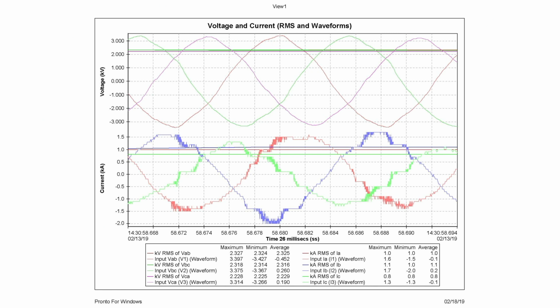Well, that same situation is happening with variable speed drives. They're doing the same thing, converting AC to DC. At the same time you do that conversion with IGBTs, switching at high frequency, it generates that kind of a sine wave. This is current, and this is voltage up here. And you can kind of see that the voltage sine wave is kind of fuzzy. It's not a solid line. So that fuzzy voltage sine wave is feeding equipment connected to it, because it's a common grid, so everything connected to it sees that fuzzy sine wave. We call it noise because it's so small, but it affects small electronic equipment. Anything that's got a program, it'll cause issues with programming equipment.